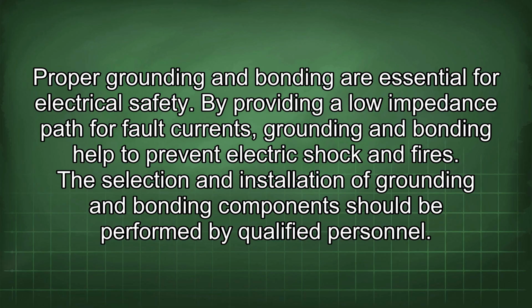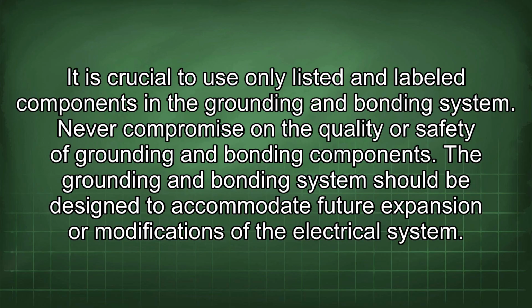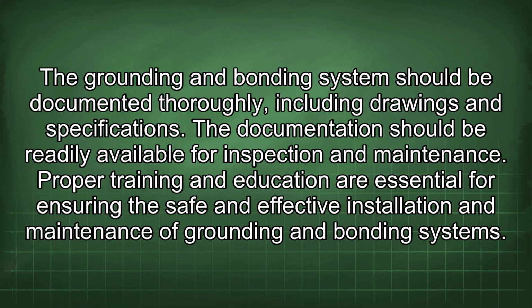Proper grounding and bonding are essential for electrical safety. By providing a low impedance path for fault currents, grounding and bonding help to prevent electric shock and fires. The selection and installation of grounding and bonding components should be performed by qualified personnel. It is crucial to use only listed and labeled components in the grounding and bonding system. Never compromise on the quality or safety of grounding and bonding components. The grounding and bonding system should be designed to accommodate future expansion or modifications of the electrical system. The grounding and bonding system should be documented thoroughly, including drawings and specifications. The documentation should be readily available for inspection and maintenance.